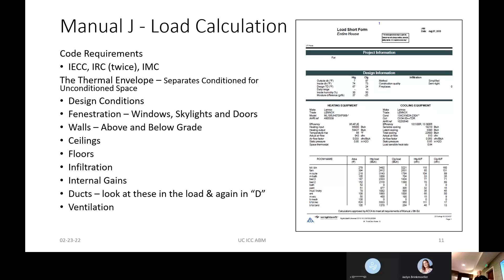A load calculation is an analysis of the thermal envelope. If this room was a standalone building, every wall would be thermal envelope, with outside above. All we would do is analyze every square foot of the entire room or building to see how much heat is lost in winter and gained in summer. We look at conduction through the envelope, air leakage, and solar gain, examining every component and how much heat transfer is going through it.